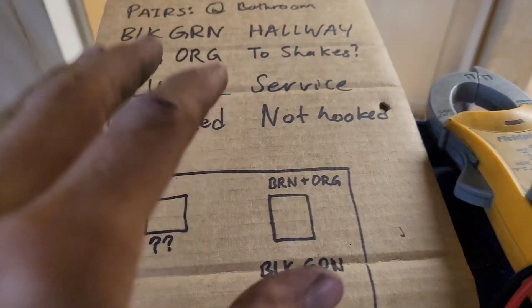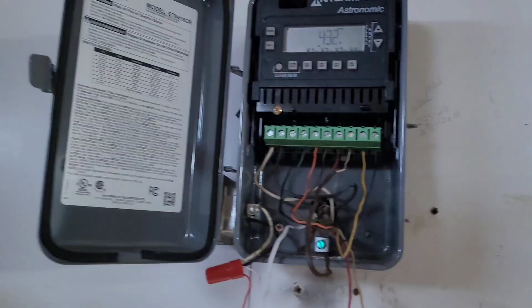But for sure we've got this load and this load that this controller is supposed to control, and that we actually want to work. It's just that this load was backfeeding with those jumpers and the wires being in the wrong spots, and that's what burnt the fuses. So we got to set up this program now so that it will run these on, because right now they're all off.